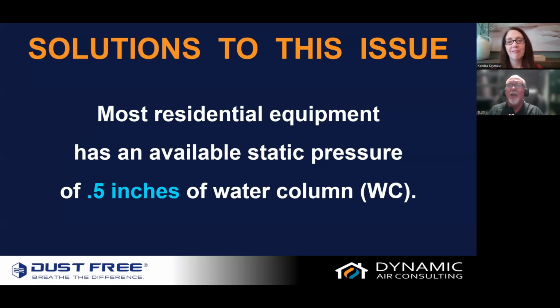And so I like to describe this, so we're going to get a little HVAC geeky again. So we're designing a system. Let's say we're designing it from the beginning, or maybe it's just a change out, or maybe we need to add in a filter, but we know we've only got a half inch of static available as a budget. And I like to say we got $5. So we have $5 in our static pressure budget to go shopping. And so we're building our system. So the first thing we do, or we're looking at this existing system, we know that our air conditioning component, our coil, comes in at about a 0.2. So there's $2 out of our $5. We got $3 left. And so now we look at a filter that can come in at a 0.2, and we figured that that's reasonable enough. So we just spent $2 more. So we got $1 left to go shopping.